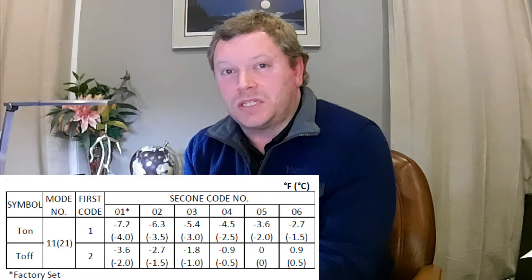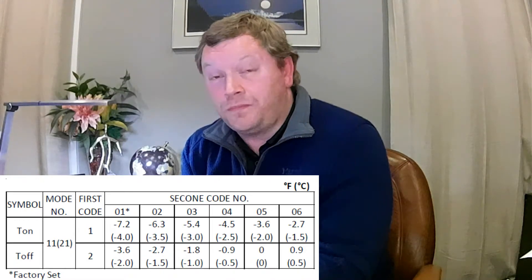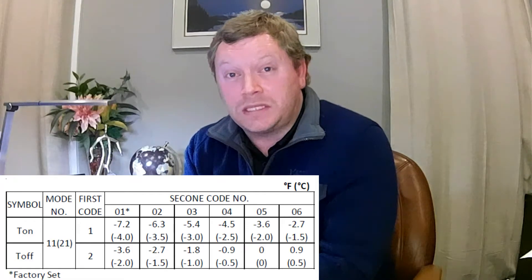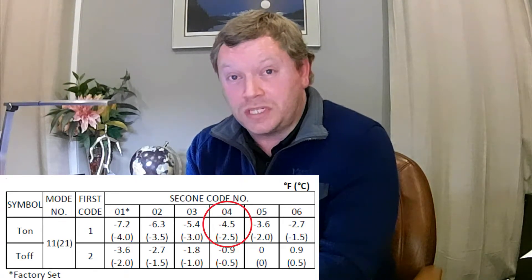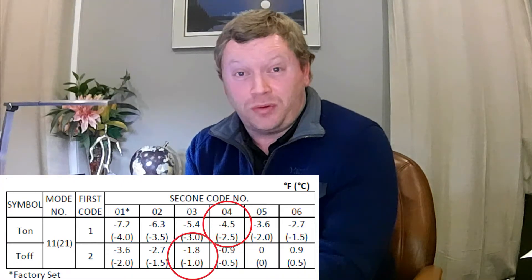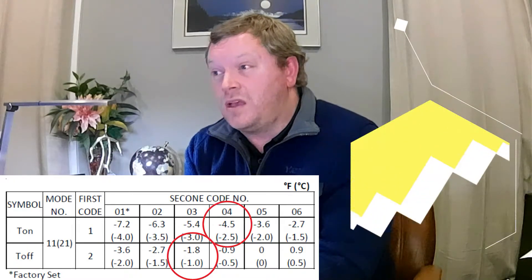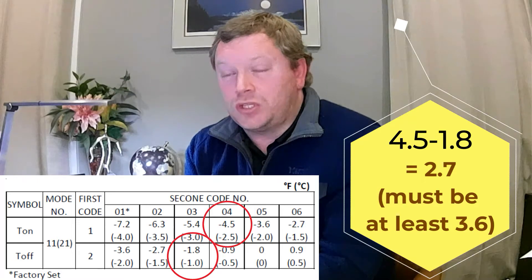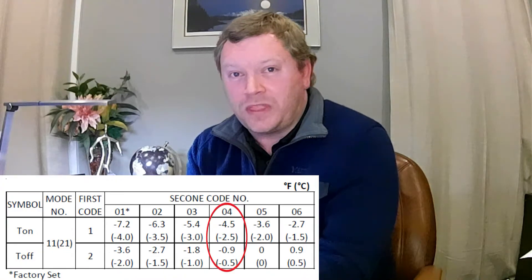What you cannot do is select 1-04 to turn on the strip heater 4.5 degrees below set point, but then set mode 21 setting 2 to dash 1.8, because 4.5 minus 1.8 does not equal 3.6 — you can't go backwards in your options. The T-off temperature must satisfy the 3.6 degree minimum separation. A simple rule: if you just pick the same option number for both your T-on and your T-off, that keeps you safe. If you look directly below 4.5 in the chart, you'll see 0.9, which is the closest you can set T-off.